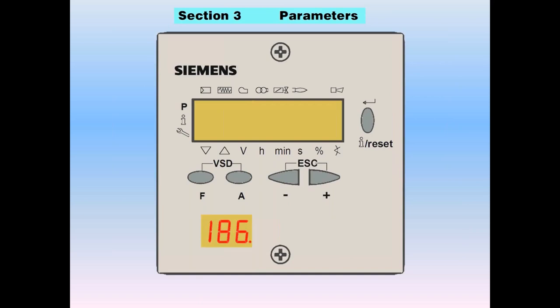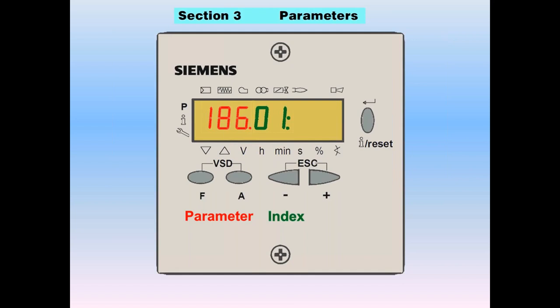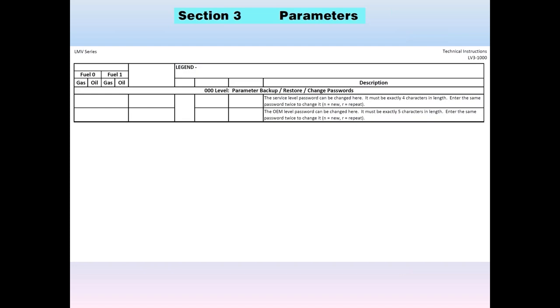Looking at the AZL of the LMV3, each parameter has at most three pieces: the raw parameter number, an index, and a value. For example, parameter 186 is flame failure response time; the index further details different settings within 186. When setting parameters on the AZL screen, you'll often need the parameter number, an additional index, and then the actual value of the parameter setting.